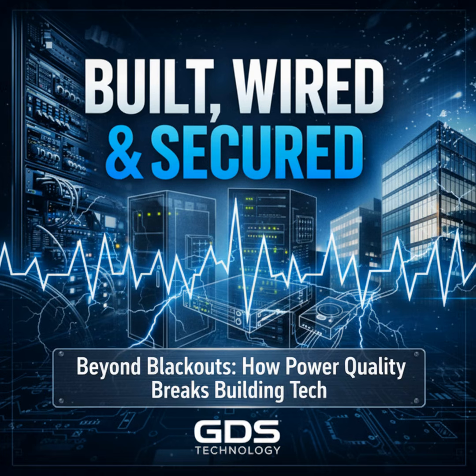How does power quality differ from a full blackout? And why should building owners and IT leaders care now more than ever? A blackout is binary. Power lost, services down. You switch to backup. Power quality is the slow, sneaky problem. A voltage sag reduces the available voltage for a few cycles. Spikes are brief overvoltages. Harmonics are distortion introduced by nonlinear loads, like variable speed drives and certain LED drivers. Modern networking and control electronics are far more sensitive, and even short disturbances can cause reboots, data errors, or marginal UPS behavior. Tenants may not see a breaker trip, but they feel the impact on devices that stop working or behave unpredictably.